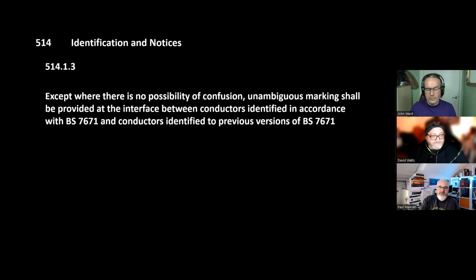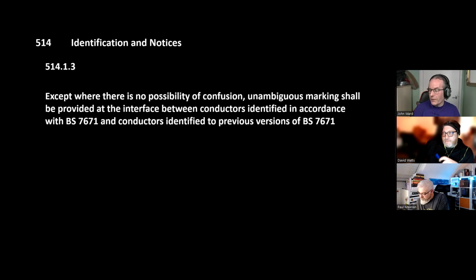Right, John, do you want to cover identification and notices? Yep. Right, 514. This is your labels and your labelling of conductors. So we've now got 514.1.3: except where there's no possibility of confusion, unambiguous marking shall be provided at the interface between conductors identified in accordance with BS 7671 and the conductors identified to previous versions of BS 7671.